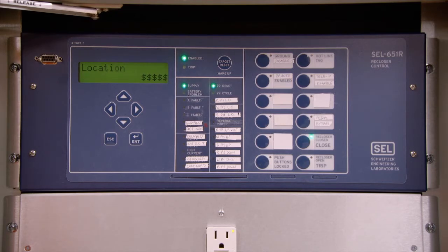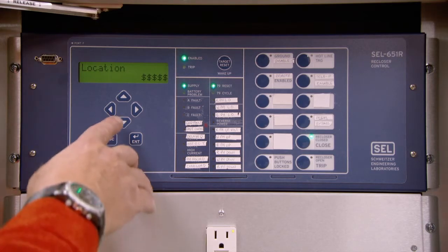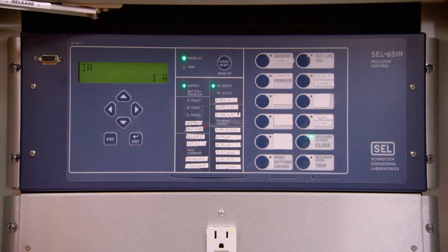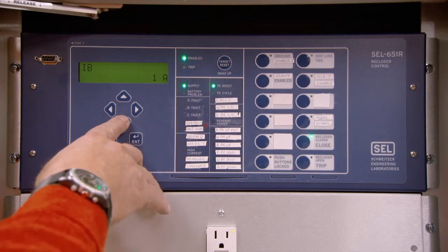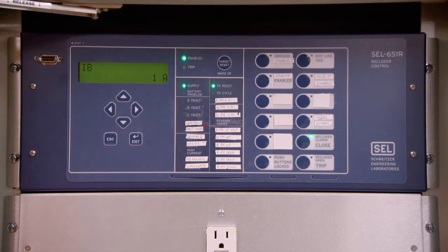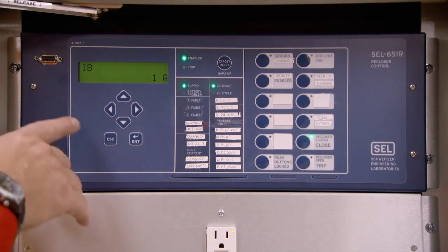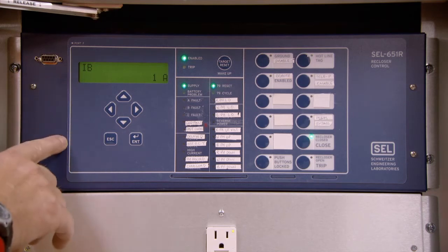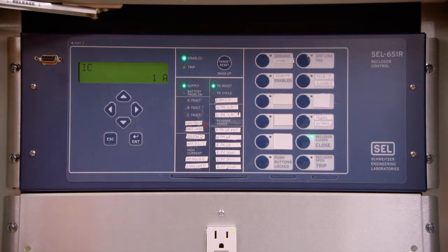and internal PTs for the distance location, you'll have to physically search for the distance to the fault, otherwise it would be provided. Pressing the down arrow again will indicate what the actual amperage was when that particular trip occurred. Pressing the down arrow key again will give the B phase current. The next down arrow stroke reveals the C phase current, followed by the G, which is the calculated value.